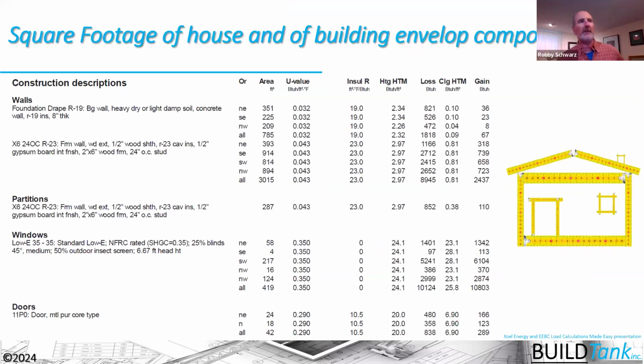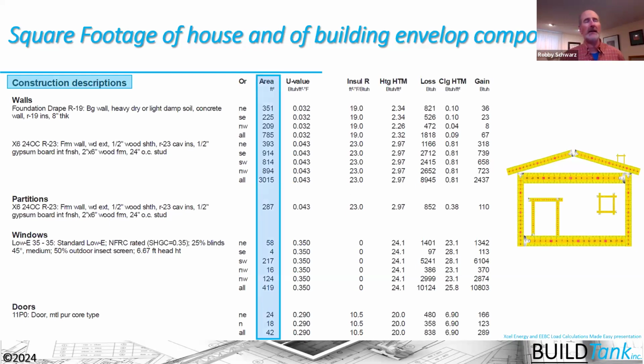The other square foot information that we're looking at here are the components that are entered in. So each of these components, from walls to windows to doors, anything that's defining the building thermal envelope is defined separately in the Manual J calculation here. So we need to understand the construction description here. We need to understand the square footage of area that's being entered into the software, and is that within reason or not there. So a quick double check. Again, we don't have to be exact. We just want to double check to understand that they're within reason here.